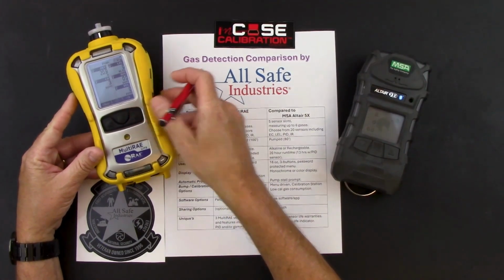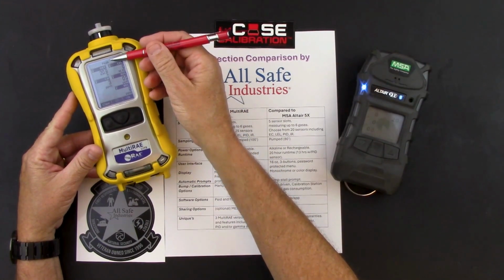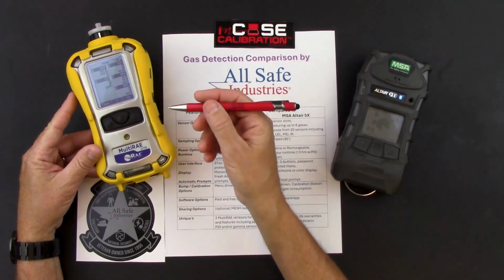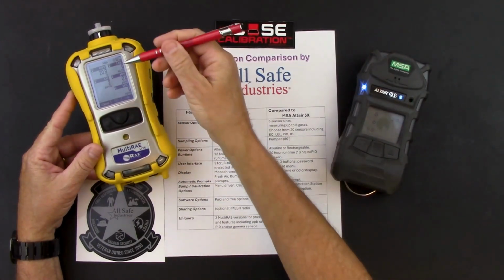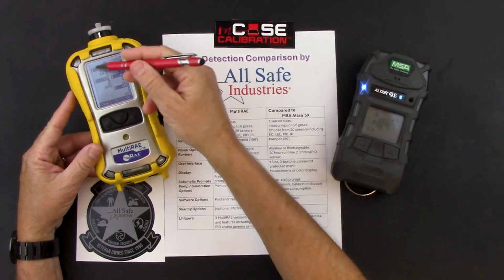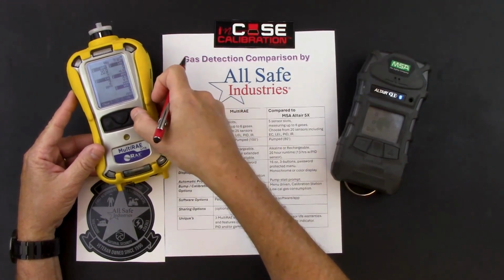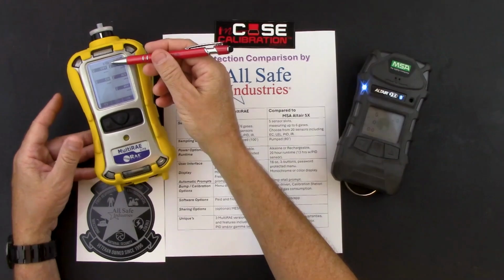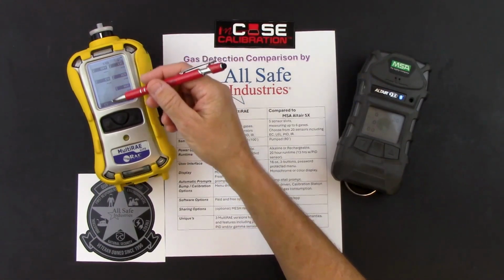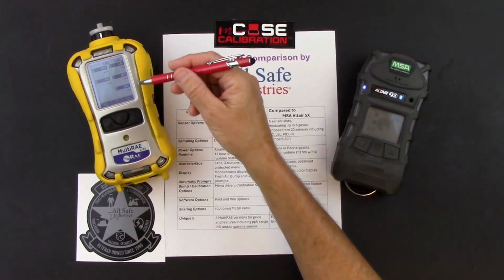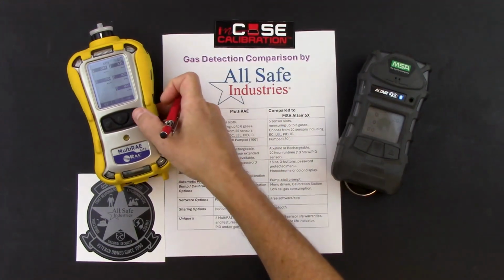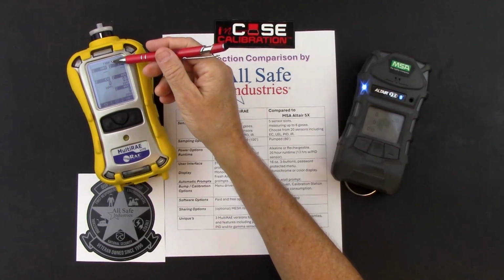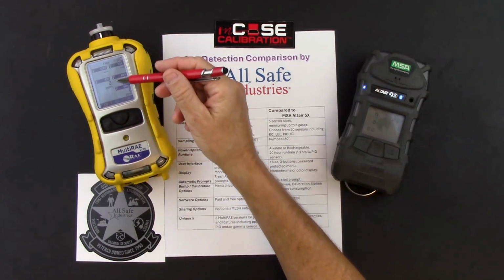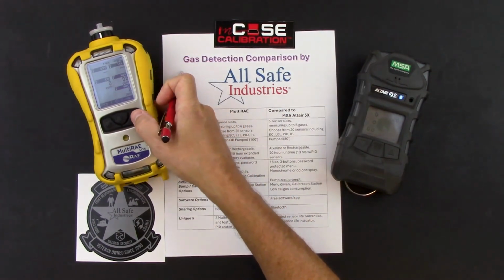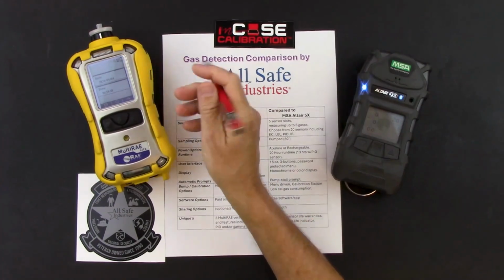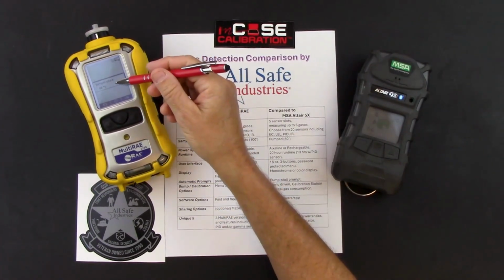So if I press the button, my first page is my peak reading screen. This is the highest reading since I've had the meter turned on. If I hit the arrow button again, this is my minimum reading screen. This is the lowest number since I've had the meter turned on. If I hit the arrow button again, this is my short-term exposure limit screen. It has not had enough time to calculate that yet, which is why you're seeing dash marks. If I hit the arrow button again, this is my time-weighted average screen. STELs and time-weighteds only report for toxic gas sensors. Arrow button again gives me date and time. Arrow button again gives me my temperature readout.